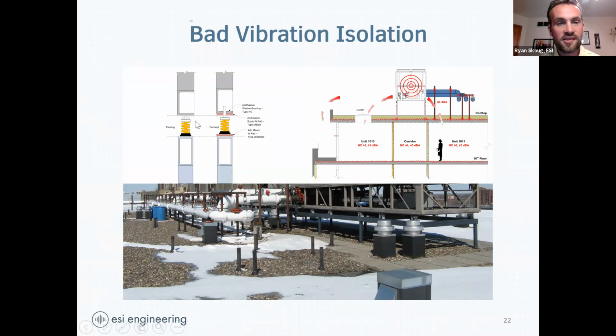The hard part was that their existing setup just had coil springs. I'm not going to take the time to go into it, but something to look up later would be surge frequencies. You can actually get your springs to vibrate, they're resonant at some frequency, and it's called the surge frequency. The chillers have variable frequency drives on them, so they'll speed up and slow down. At some frequency they line up with the frequency of the spring, that surge frequency, and it just sings coming down through the post and gets right through.